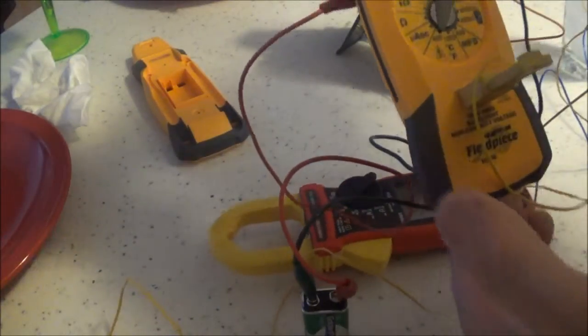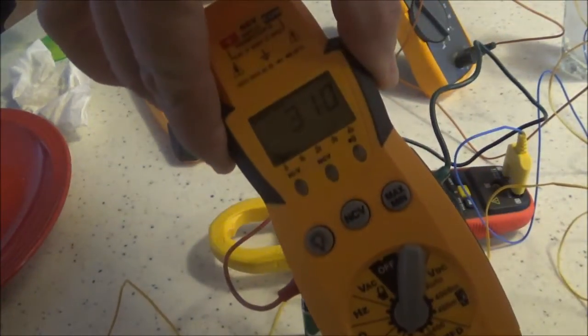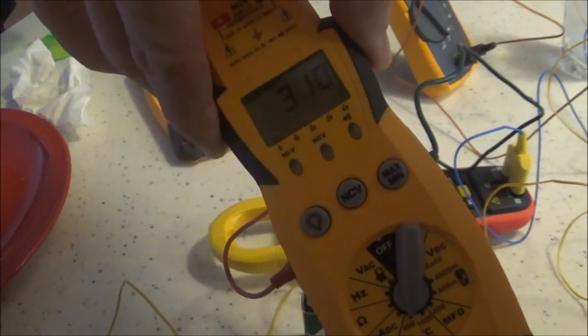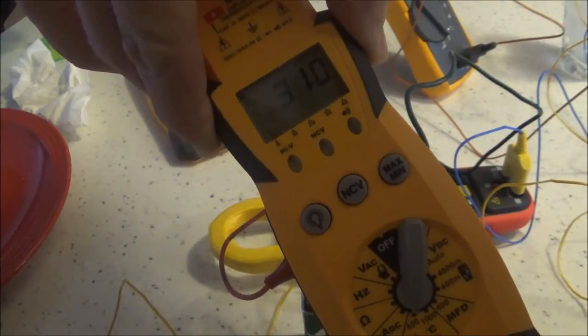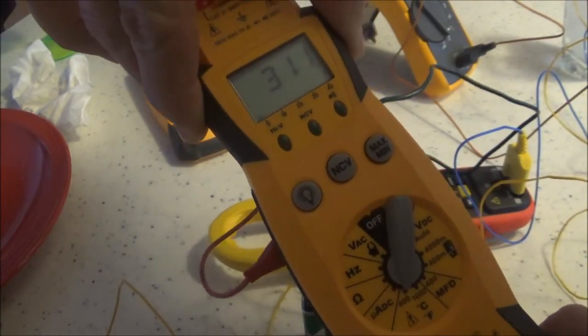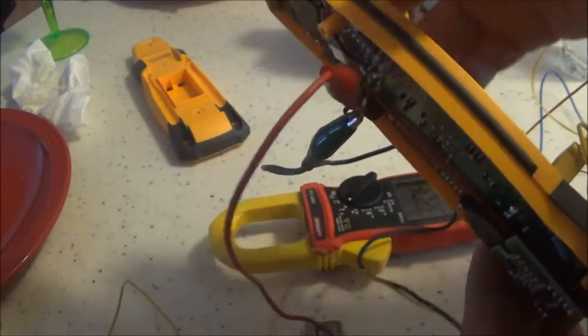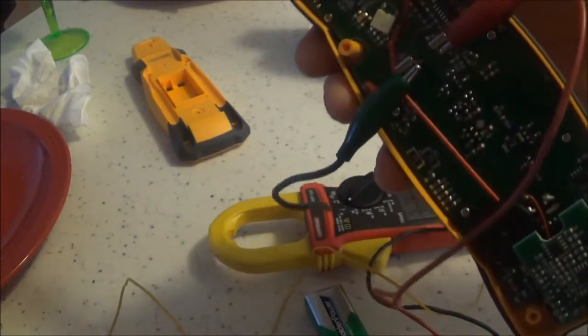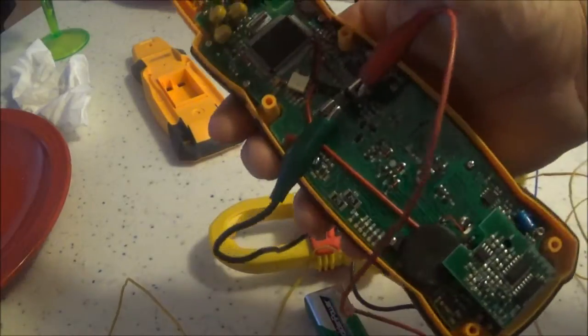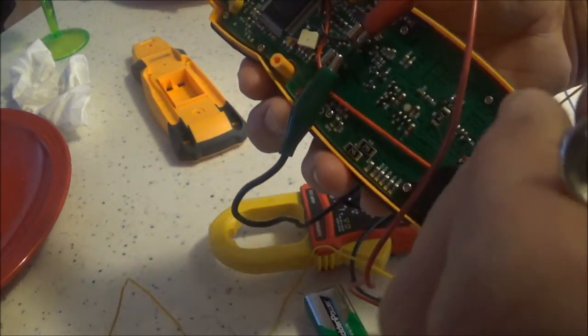Touching the plastic only. You can see temperature's dropping down. 31 degrees. Still at 32 on the amp probe. So yes, it's close. But you know, one degree, I kind of want it to be right on.